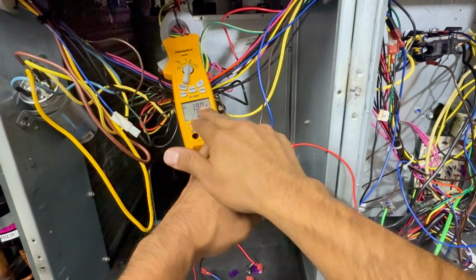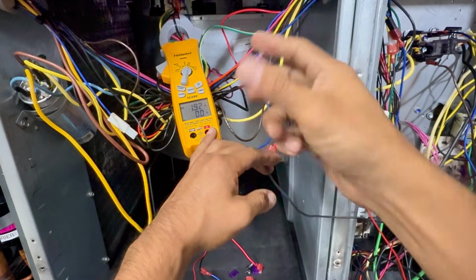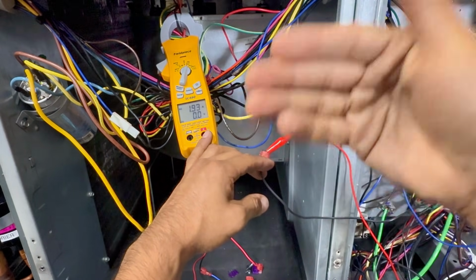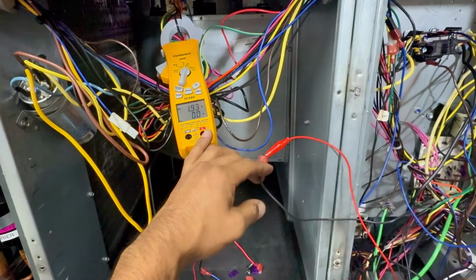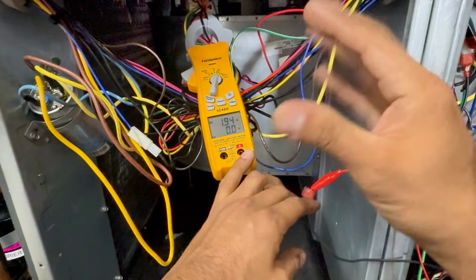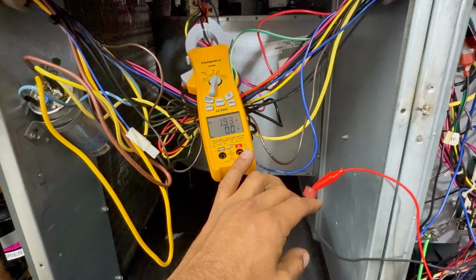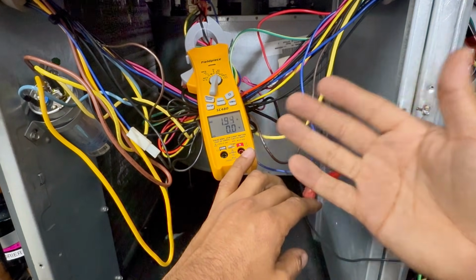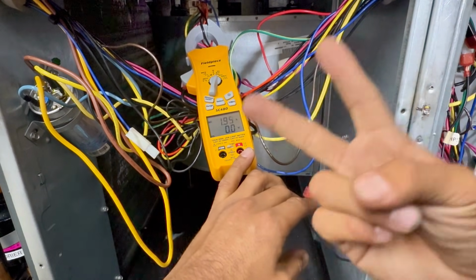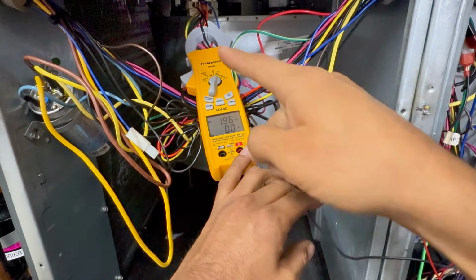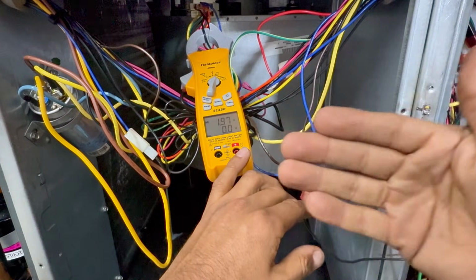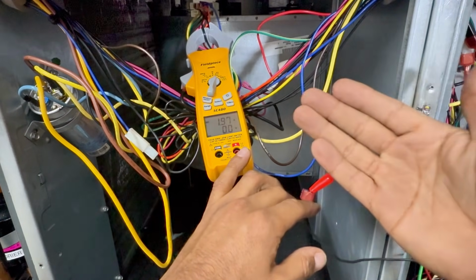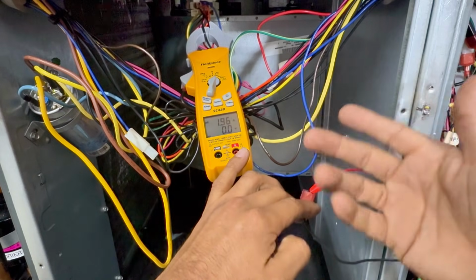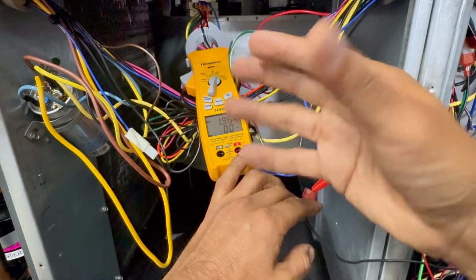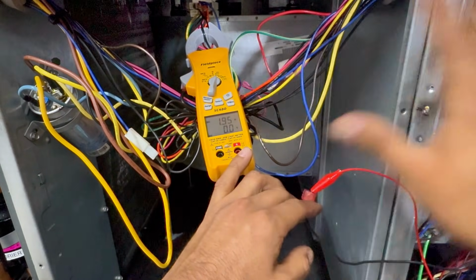But this number here, right, that ECM motor, it has that full load amps and what it should be pulling. So let's say just an example, right? Let's say it's supposed to be pulling 5 amps, okay? And let's say it's pulling 2, and let's say you're calling for cooling. If it's pulling 2 when it should be pulling close to 5, that tells you, hey, there is an issue. Do I have a full-on restriction? What is going on? Because it works on air. If I can suck, I can blow air out. If I can blow air out, I can suck air in.